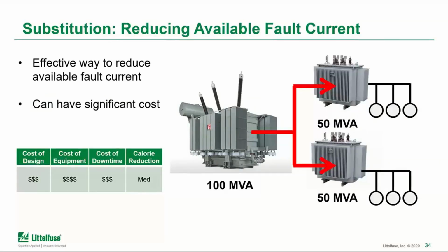So starting at the top of the pyramid with the most effective types of controls, substitution here means reducing the available fault current by substituting one large transformer for two or more smaller transformers in branch circuits. That would serve to limit the amount of short circuit current, the amount of energy available on a particular branch.